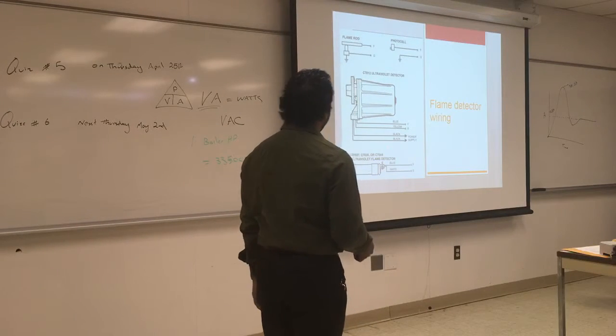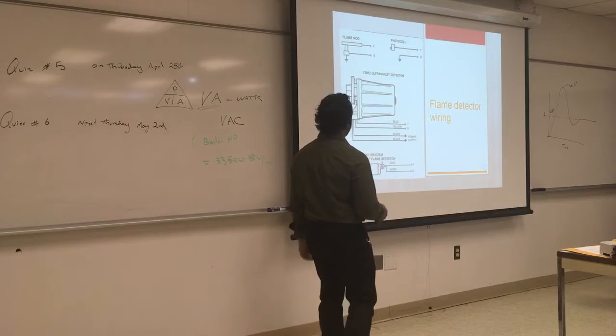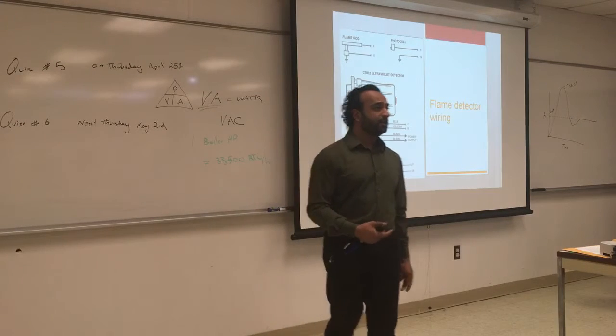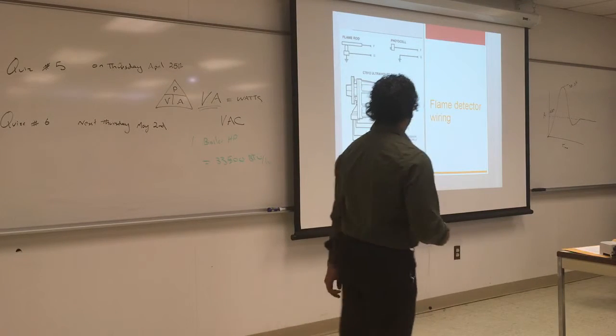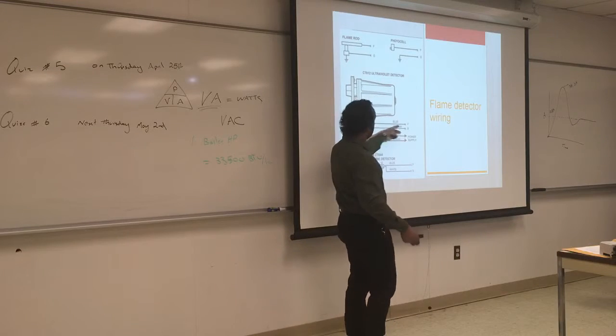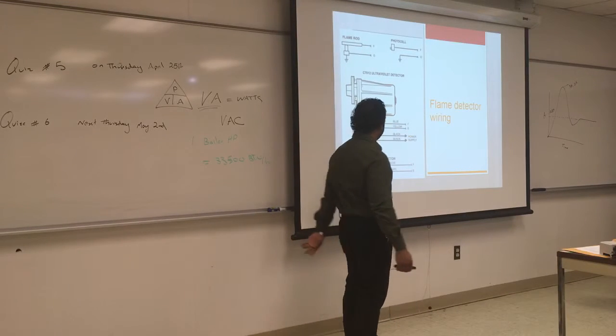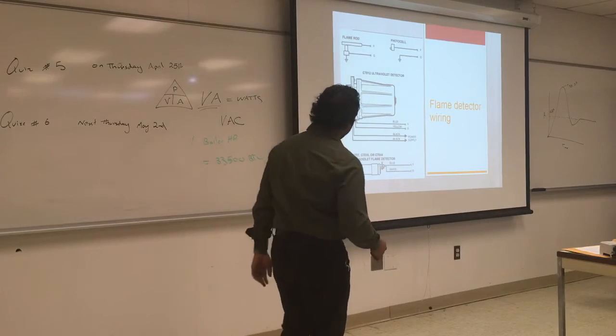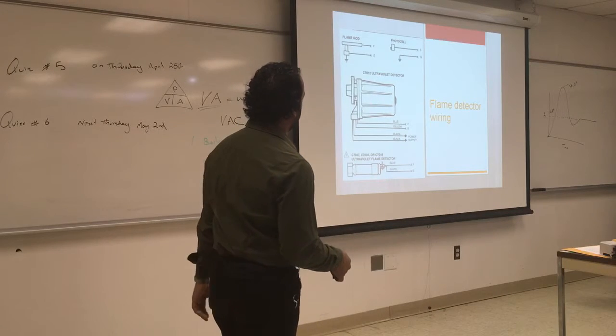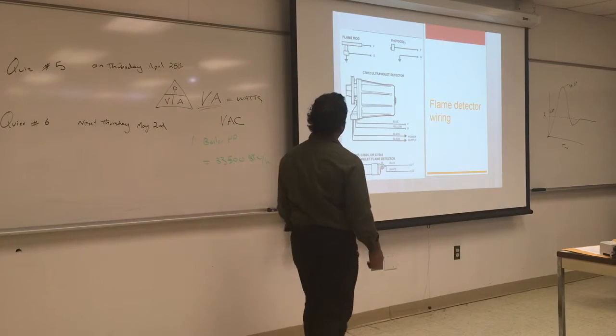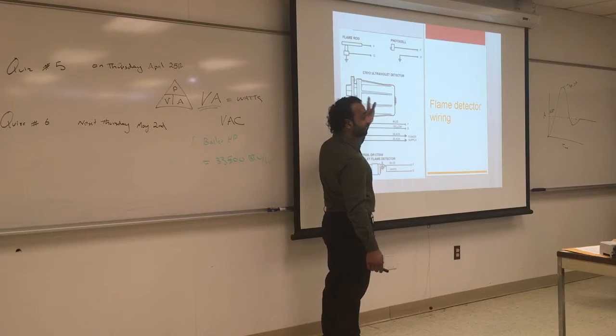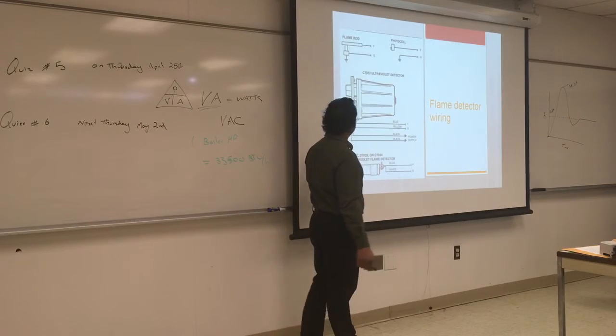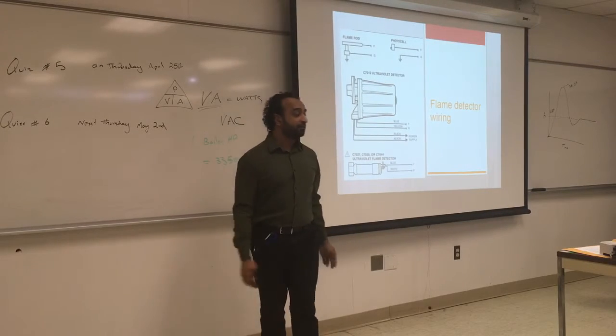It's the same thing here for FG. You have the FG, and you also have a power supply if you use an ultraviolet sensor. The UV sensor needs a power supply to operate, but again, it will send you FG signals. There's a small UV sensor and there's a big one, depending on the occasion. The small one will be outside the burner chamber, and this is the same eye over here. And this here is the visual that you get from the flame.